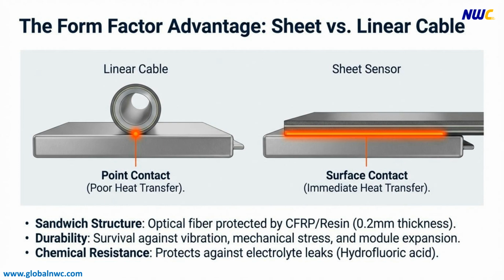Unlike conventional linear sensing cables that rely on point contact, the sheet-type sensor achieves broad surface contact, enabling instantaneous heat transfer and highly precise monitoring without delay. Its ultra-slim 0.2 mm sandwich structure protects the optical fiber within layers of CFRP and resin, providing strong resistance not only to physical stresses, such as vibration and expansion, but also to electrolyte leakage. This optimized form factor ensures the highest level of reliability for battery systems, even in the most demanding environments.